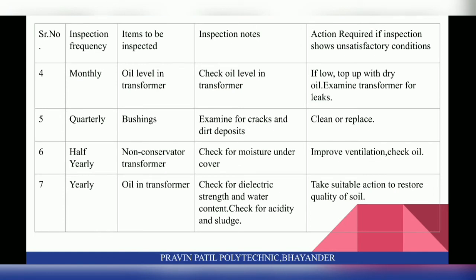For monthly basis, you have to check the oil level in the transformer. Inspection note: Check the oil level. Action required: If the level is low, top up with dry oil and examine the transformer for leaks.